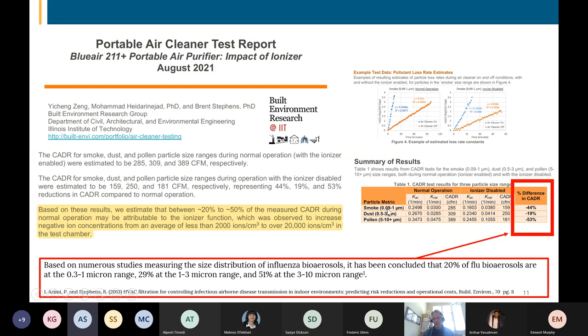So in the ionized environment, based on over here on the right-hand side, certain particle sizes of concern, for example, 0.09 to 1 micrometer, the ionized environment made the CADR rating of that standalone filtration machine 44% better. Don't pay attention to the negative. You got to read the report. With regards to dust, 0.5 to 5 micrometers in size, it made the CADR rating 19% better. And with regards to pollen, the 5 to 10 micrometer size, it made the CADR rating 53% better. It improved the CADR rating somewhere between 20 and 50% based on ionizing the air versus an environment where the air was not ionized with some type of bipolar ionization device.